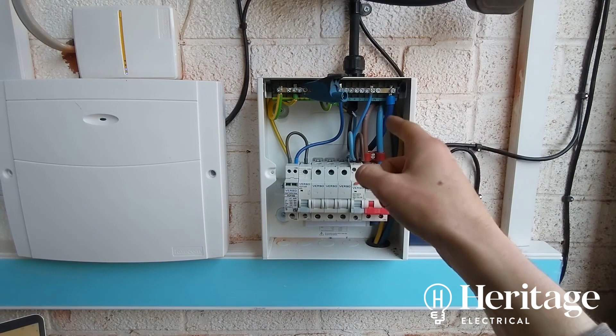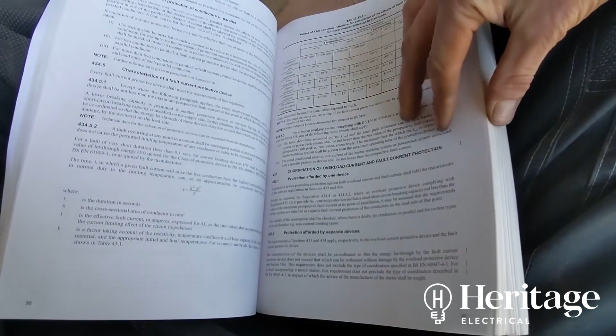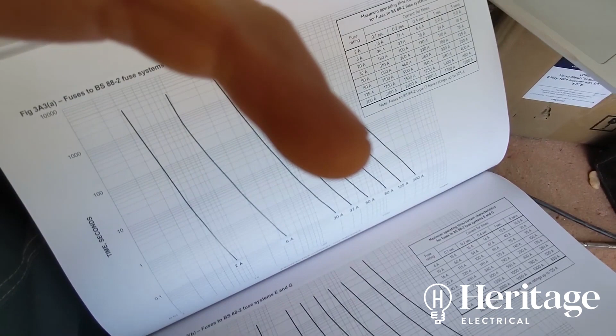Nevertheless, just wanted to do a couple of calculations, make sure that these tails are protected against fault current. So we'll just go to the regs, and we're using the adiabatic equation here. A combination of that, and towards the back we've got time current characteristics of different protective devices somewhere. Where are we here? Yeah, so here's an example of a page, some fuses. So we plug in our fault current down the left hand side here. We find whichever fuse we're using, and then we work out how long it takes for that fuse to trip, or fuse. And in this instance, the fault current gives us a fusing time of around about 3 seconds.